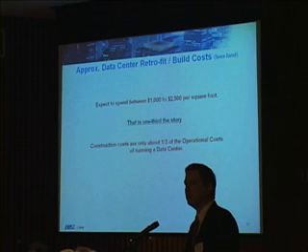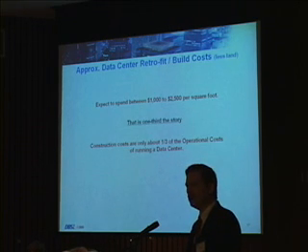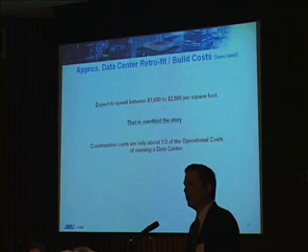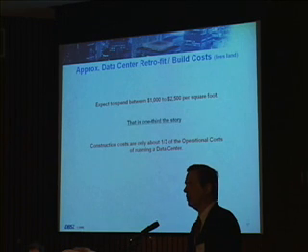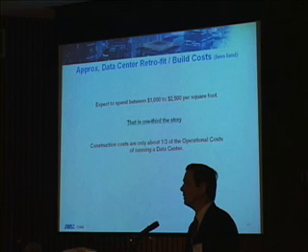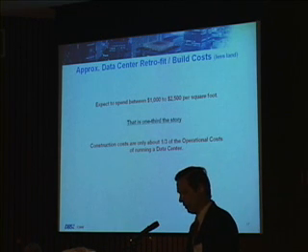The other thing to remember is that when you build a data center, the actual cost to build it, amortized over time, is really only one third of the operating cost of a data center. You've got fuel, and we test our generators weekly and monthly, and fuel went from $1 to almost $4 a gallon. Running at 132 gallons an hour per generator, we consume thousands of gallons of fuel a month just testing generators. So there's a lot of costs there that you may not be directly billed for because your facilities people may be taking care of that for you.